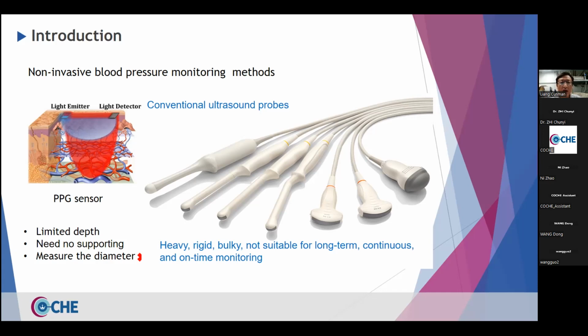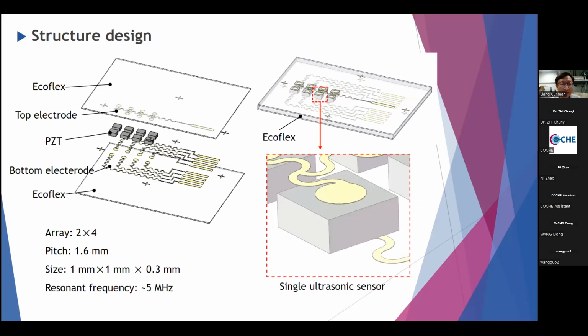However, traditional commercial ultrasound probes are usually heavy, rigid, and bulky, which is not suitable for long-term continuous, on-time monitoring of blood pressure. To overcome these problems, we would like to develop a flexible ultrasound sensor. The sensor should be flexible and stretchable enough so that it can be attached to human skin for long-term monitoring of blood pressure. This part is the structural design of the flexible sensor. An island-bridge layout with serpentine electrode is used in the flexible ultrasound sensor to ensure the device is flexible and stretchable.